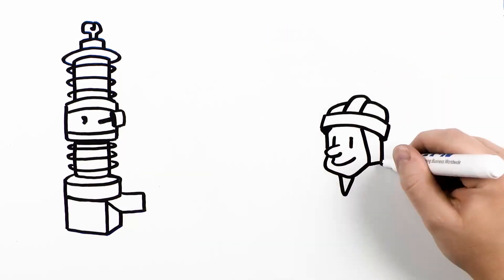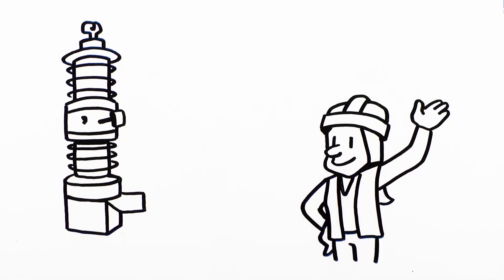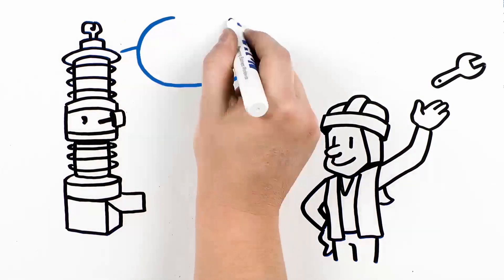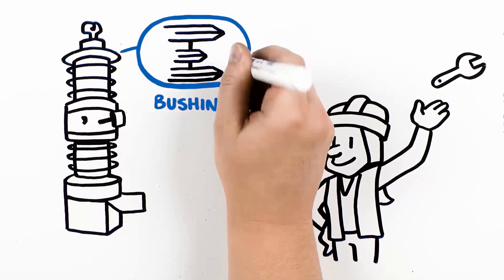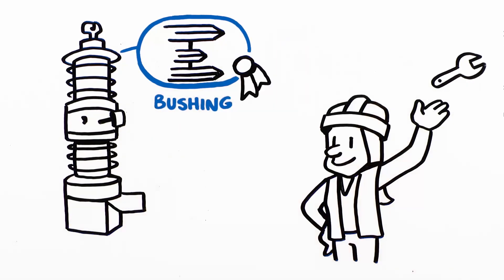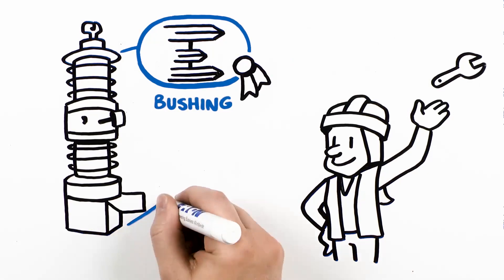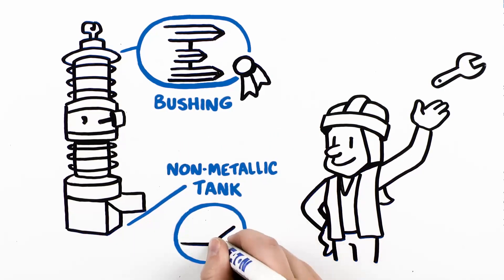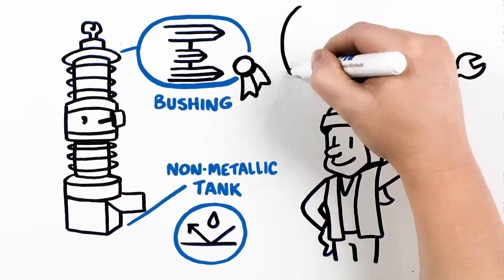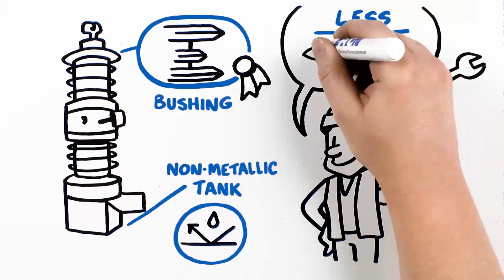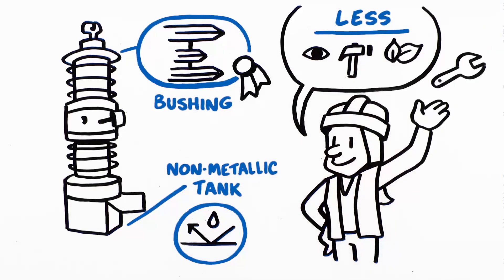Tri-Sync provides an environmentally friendly solution with little to no maintenance. The switch features an alternating shed bushing design, tested and proven to perform in the highest levels of pollution. The fiberglass non-metallic tank prevents corrosion for maximum reliability. And no SF6 gas or oil means less monitoring, maintenance, and environmental impact.